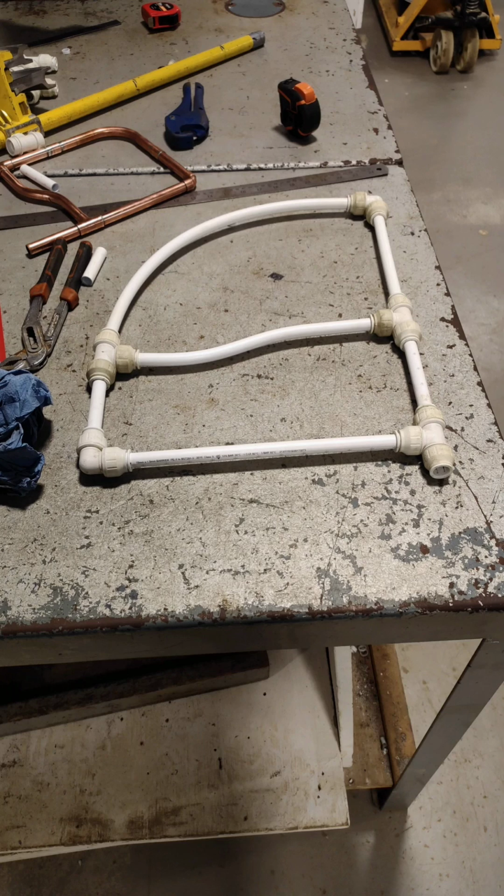For instance, if the water main is made of cast iron, then a self-drilling and tapping machine is used. With this tool, the water main is drilled, threaded, and a ferrule inserted while the main is still under pressure, so that supply to other properties is not disturbed. If the main is made from PVCU or cementitious lined asbestos, then a brass strap type ferrule is used.